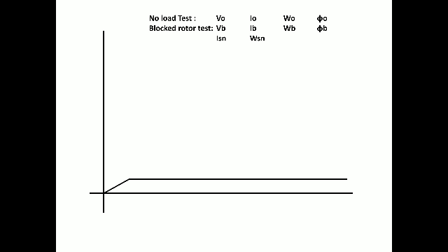Then after this, draw one more line by using ISN with the angle of phi B. This line is longer when compared to the I naught line. After drawing this line, you have to join the edge of the I naught line and the ISN line. That line should be considered as the output line. So the last line you see is the output line. Now you're going to bisect the output line. So draw a line which bisects the output line. That bisecting line will intersect the reference line. That point is considered as C, the center of the circle.